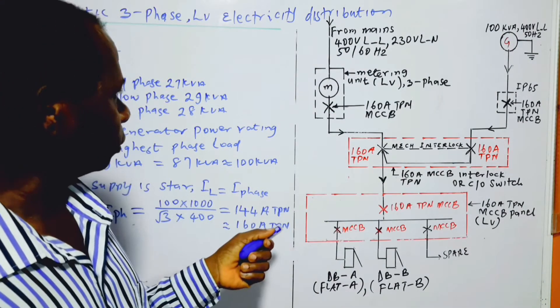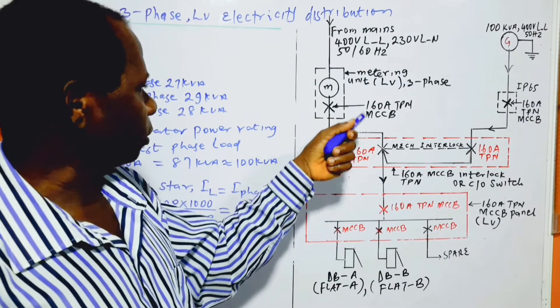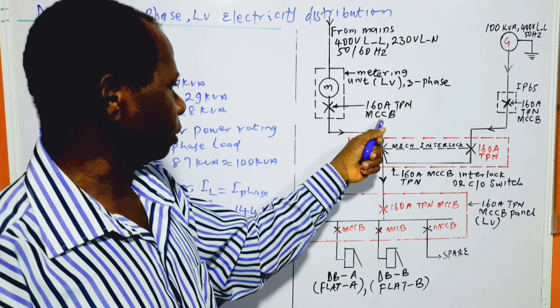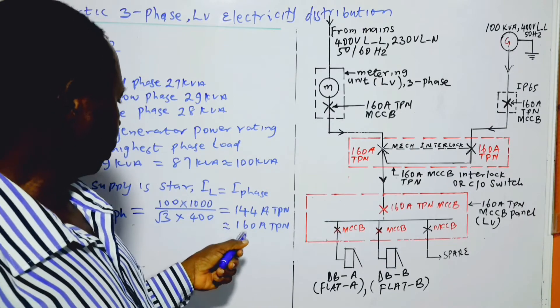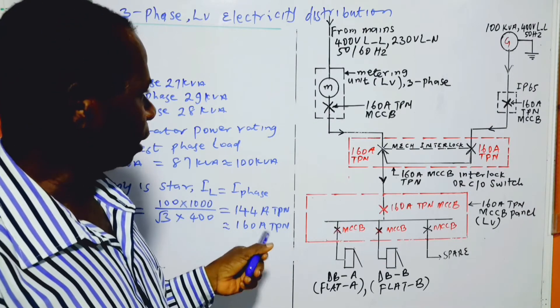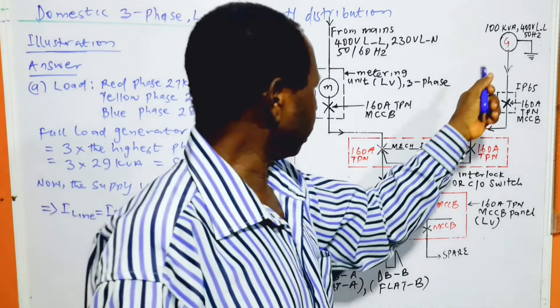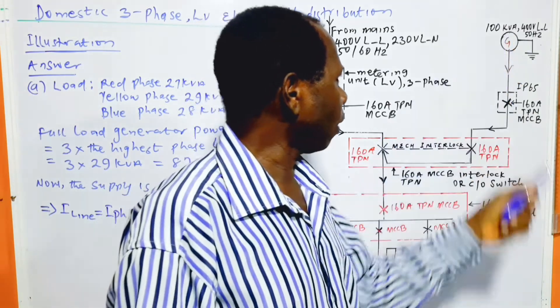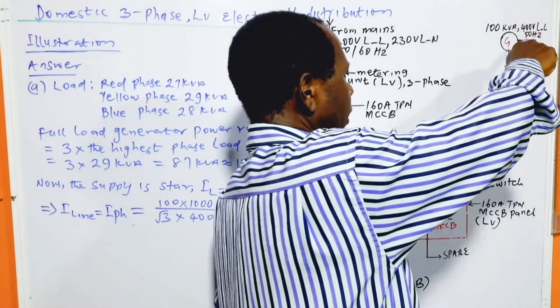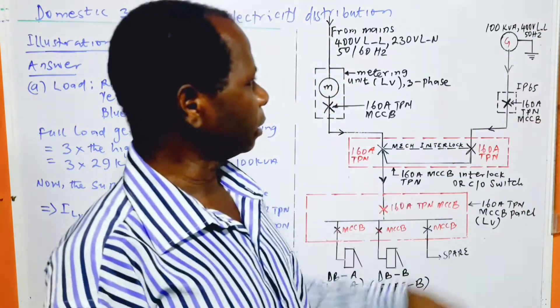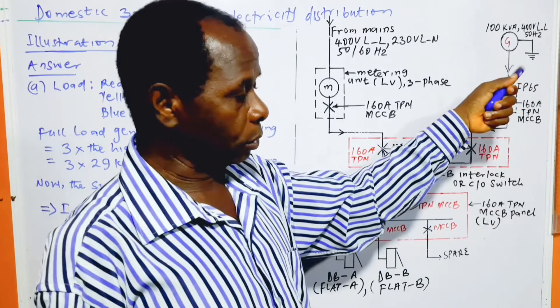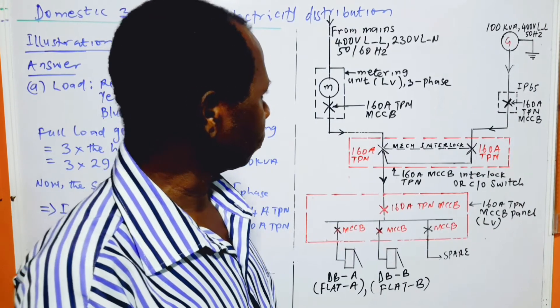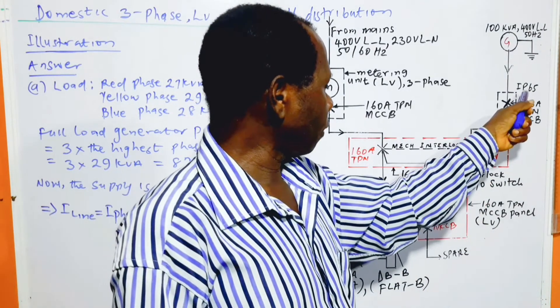We have the 160 ampere triple phase with neutral MCCB, the value of which is calculated here. We have the generator size, or the rating, which is 100 kVA, 400 volt line to line, 230 volt line to neutral, and at 50Hz or 60Hz as the situation will be.